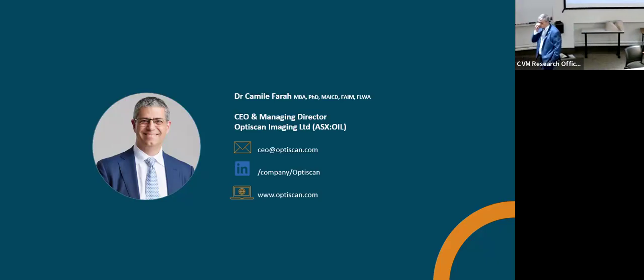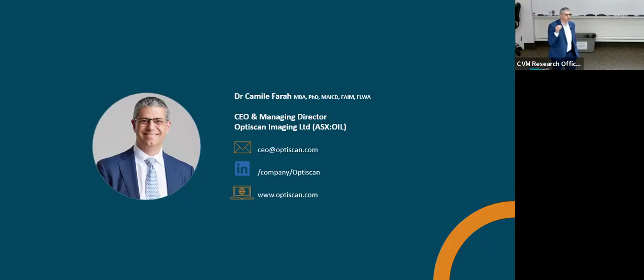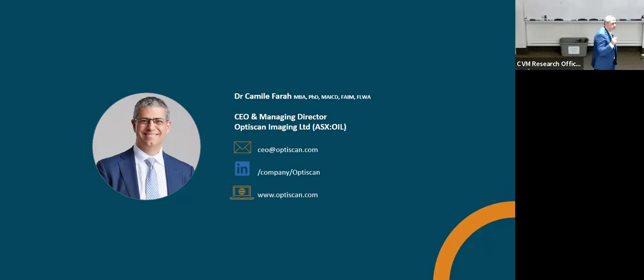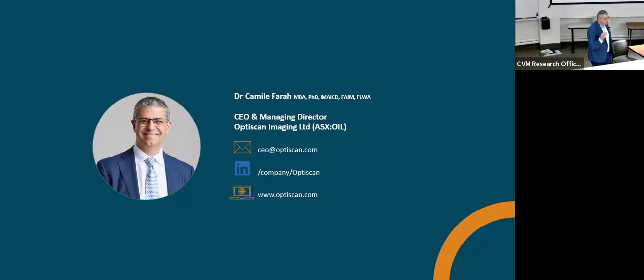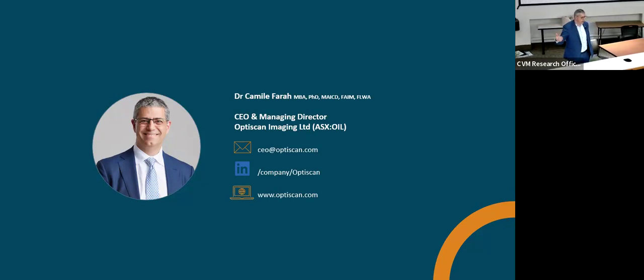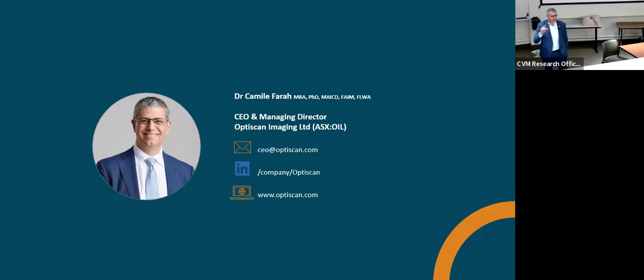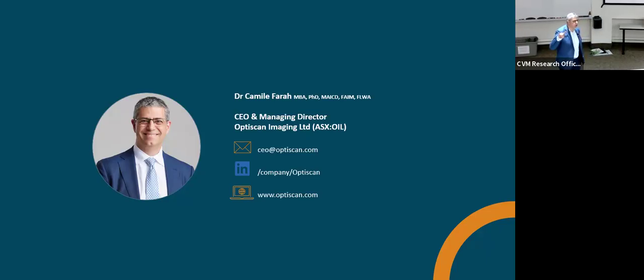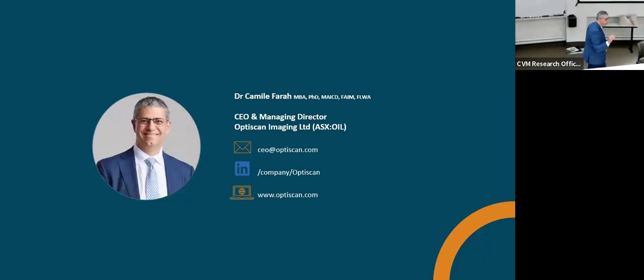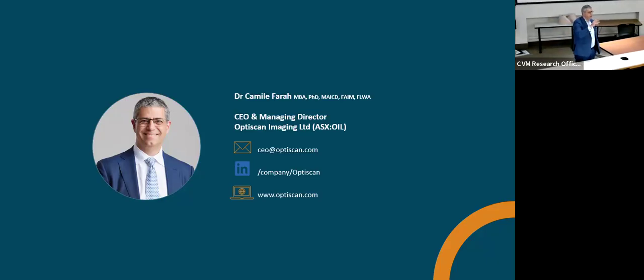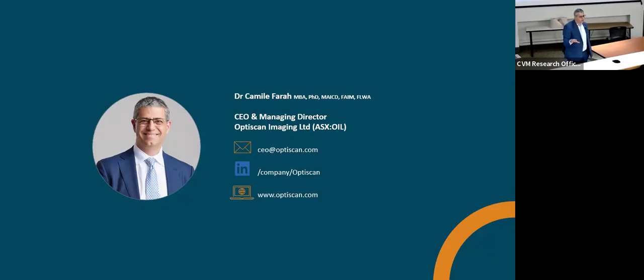Thank you. Okay, so the frame rate is 1 to 3.5 frames per second. That's if you're operating at 1024 by 1024 resolution, you'll only get 1 image per second. If you drop that and go to 1024 by 256, you'll get up to 3.5. So if you've got a dynamic process and it's quick, you should be imaging at the fastest speed. However, you will let go of some of the resolution and quality of the image, right? So there's a trade-off there.